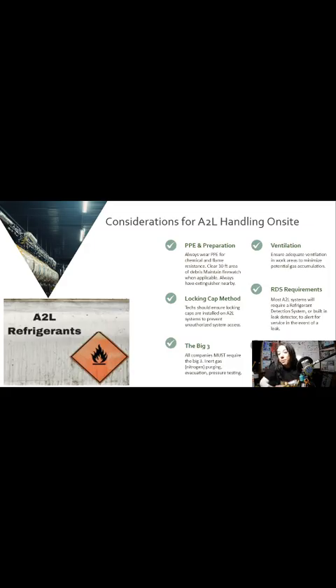The big three—this is the most important, okay? All companies must require the big three: inert gas nitrogen purging, evacuation, and pressure testing. Gone are the days where you could get away without an evacuation. I don't know anybody still doing that—I hope nobody is, but I've heard some stories. You have to purge nitrogen while brazing, no choice. You have to perform a deep evacuation, no choice. And you have to pressure test, no choice. I don't mean if you see your decay test rising a little and need to freak out—what I mean is hold a pressure test. If you hold a pressure test, you're good. No sweat, purge, and roll, baby.